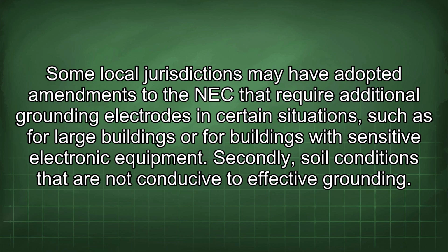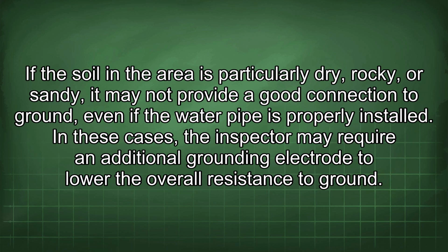Secondly, soil conditions that are not conducive to effective grounding. If the soil in the area is particularly dry, rocky, or sandy, it may not provide a good connection to ground, even if the water pipe is properly installed. In these cases, the inspector may require an additional grounding electrode to lower the overall resistance to ground.